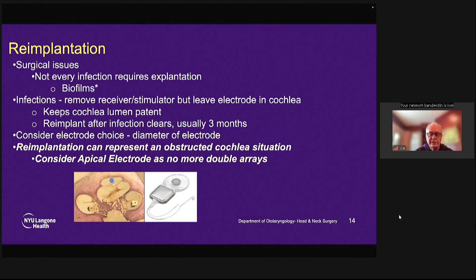The other issue that we sometimes have encountered, and that some people have talked about, is that perimodiolar electrodes are more traumatic to remove than outer wall electrodes, which isn't true. And that feeling was not based on any real data. So here's a model, from another publication from 2 years ago. We filled a 2D cochlea with a gel that simulated soft tissue for an outer wall electrode and a perimodiolar electrode. And then we withdrew these electrodes slowly and measured the forces it took to withdraw and also observed the electrode behavior. So the perimodiolar electrode kind of just slips right out and does not displace the tissue, which you'll see on this image.